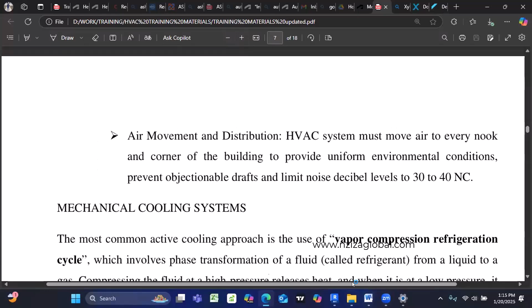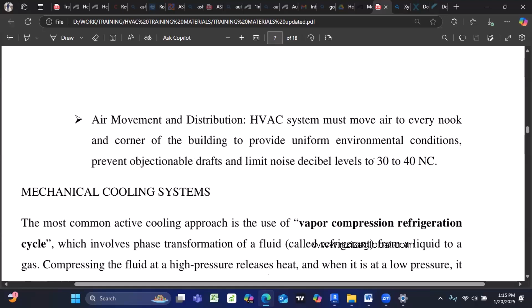Another thing in terms of comfort in air conditioning is noise, from air movement and distribution. For example, when we are in the rooms, the air moving inside the ducts creates noise, so there is a limitation on air velocity. For you to feel comfortable, the air movement noise level in the duct system needs to be limited to 30 to 40 NC. I'll show you this NC here. It's called noise criteria.